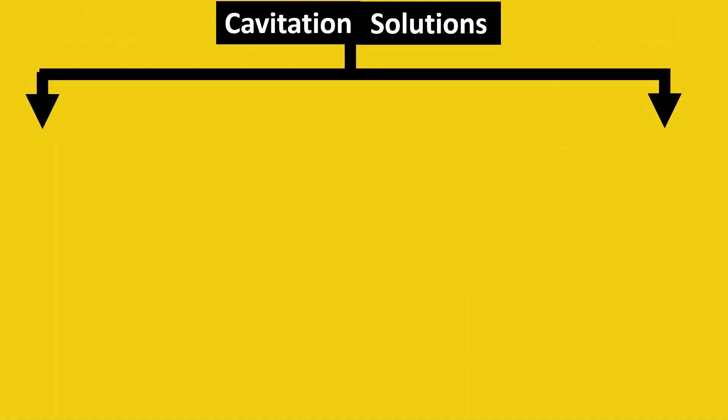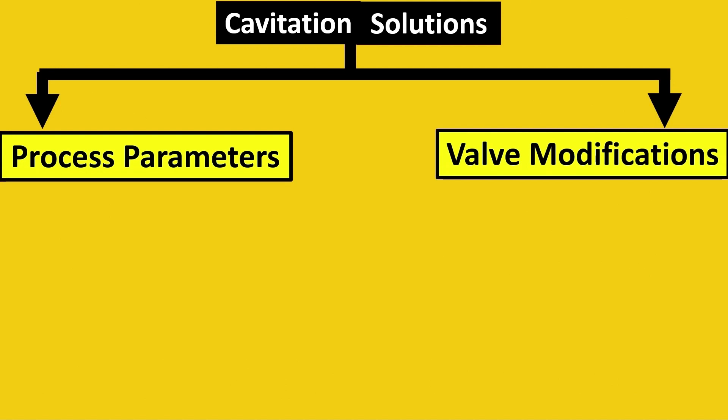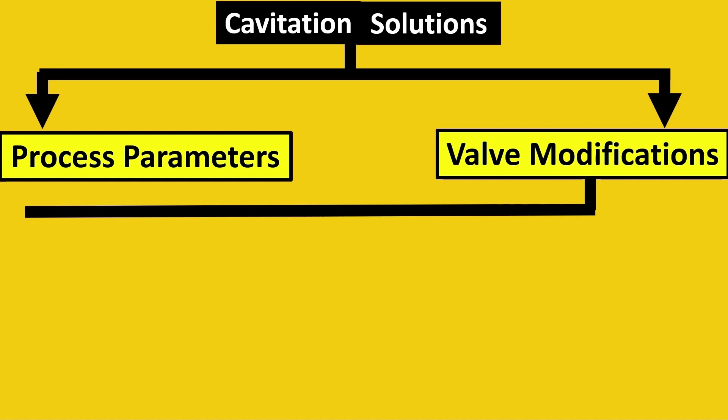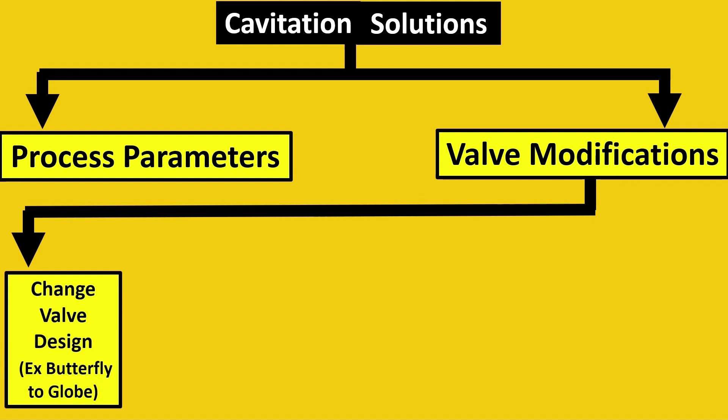For cavitation solutions, we have learned there are process parameters and valve modifications. We look first for valve modifications, which is first changing the valve design. Example: butterfly, as we said in the previous example, would have just one point of pressure drop. However, globe will have multiple points. It's better to go for globe then.